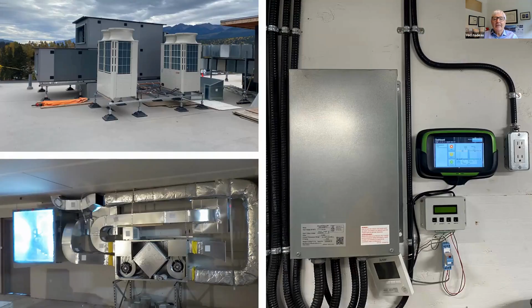Here's the Swegon ERV with preheaters installed in Golden. There's a Mitsubishi 18 tons of heat cool. So this is 5 systems for the price of 1. We get our ventilation with the ERV at 85% heat recovery. There's no makeup air in it for corridor pressurization.